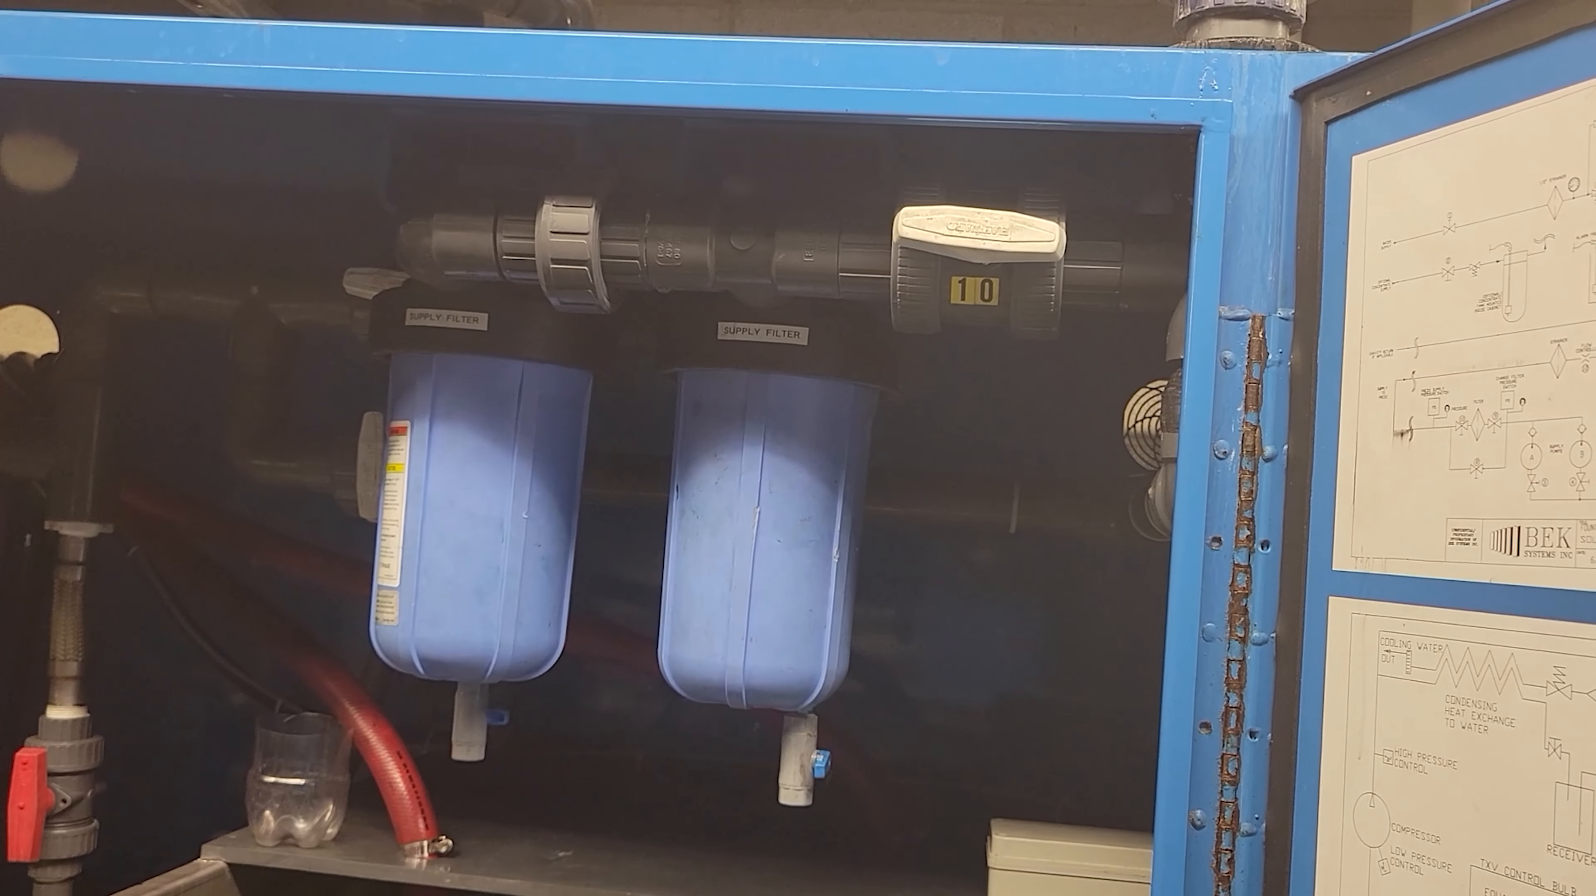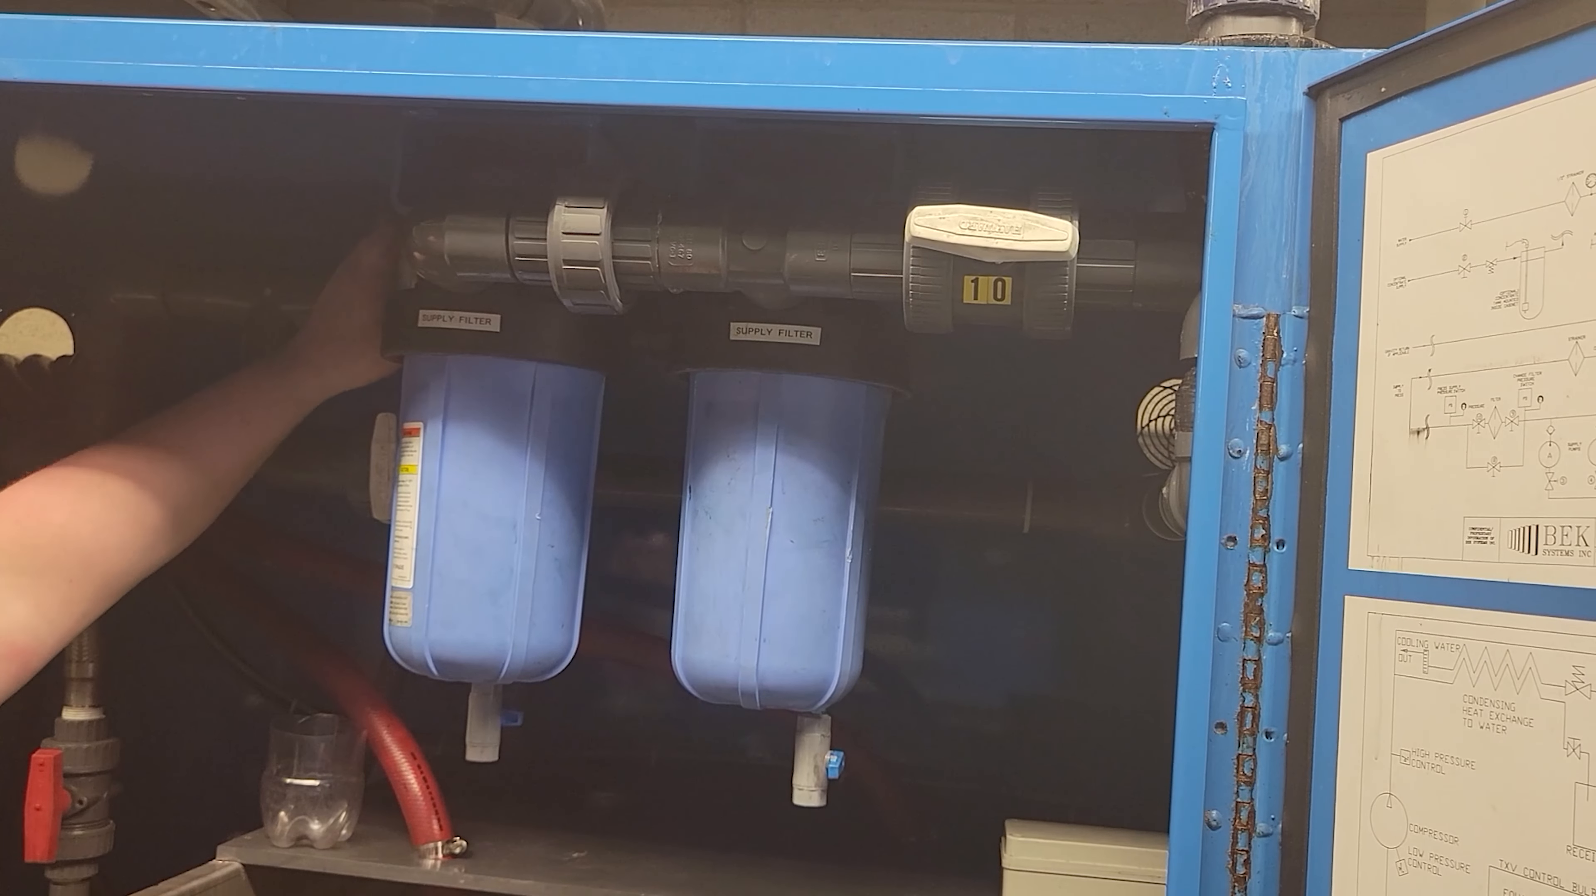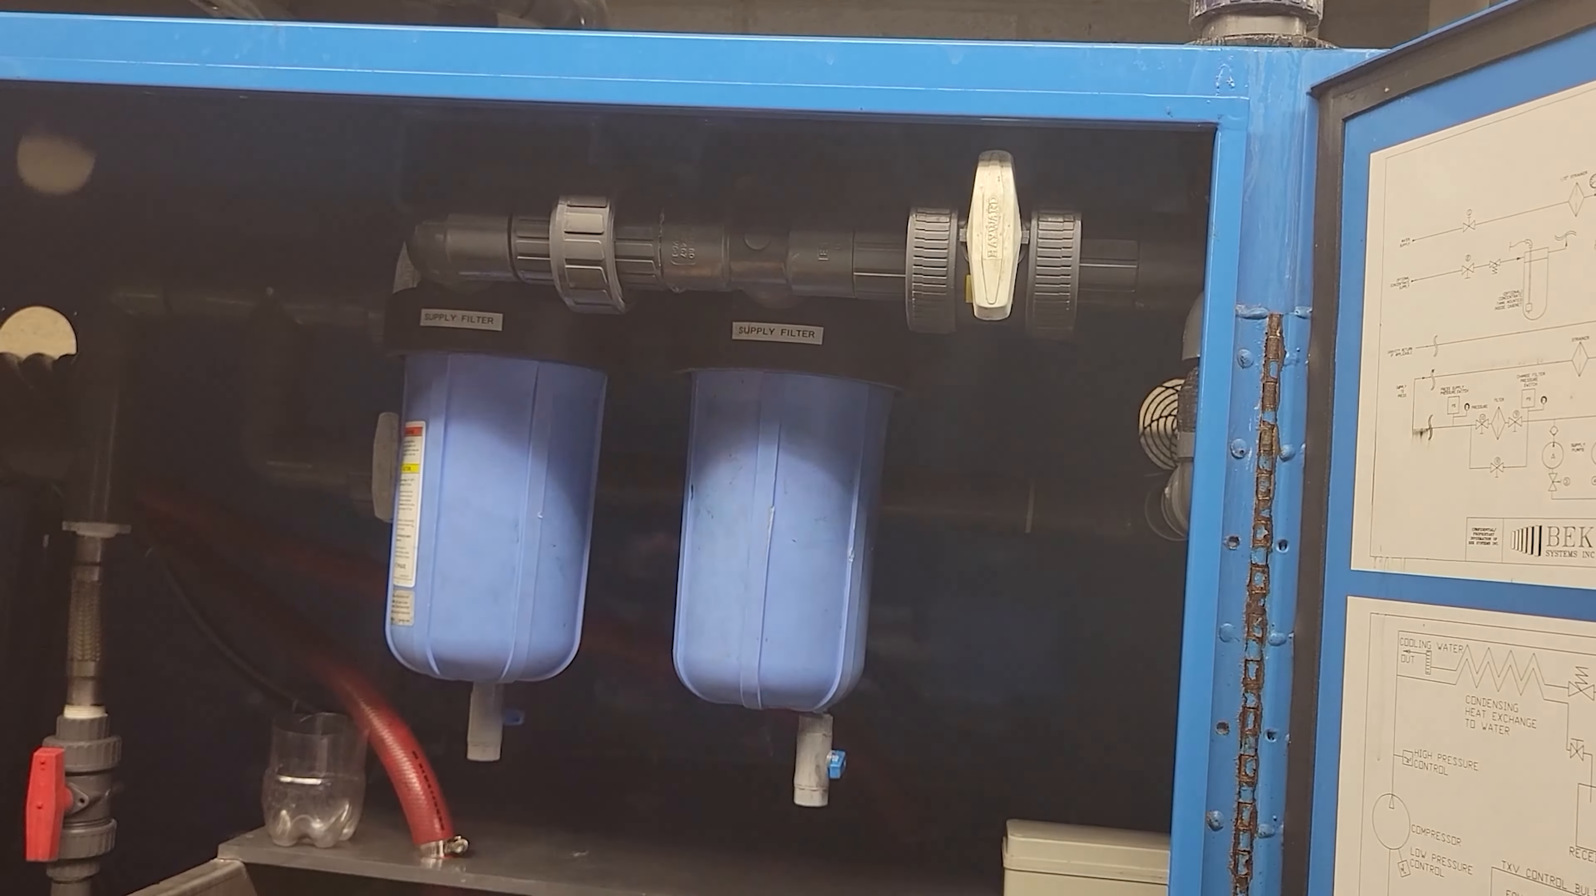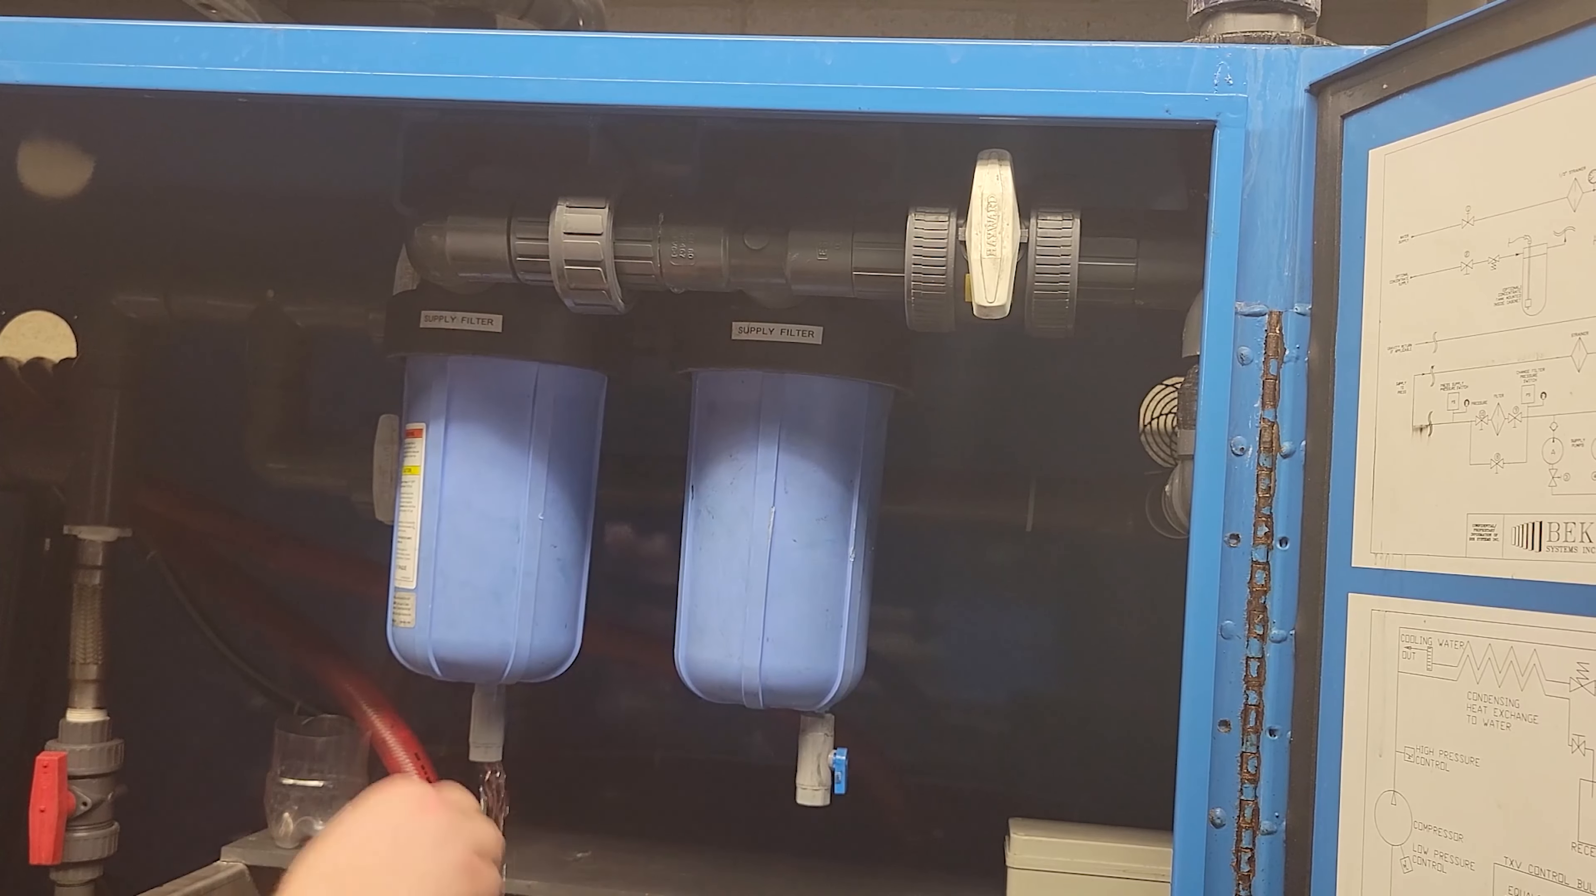Here are my filter housings. The first thing I want to do is make sure all of this is isolated, so I'm going to shut off these two valves. The only thing I've got in here are these filters. We installed these drains. Now I'm going to allow the water to escape. It's going to help depressurize the system and make it a little bit cleaner.